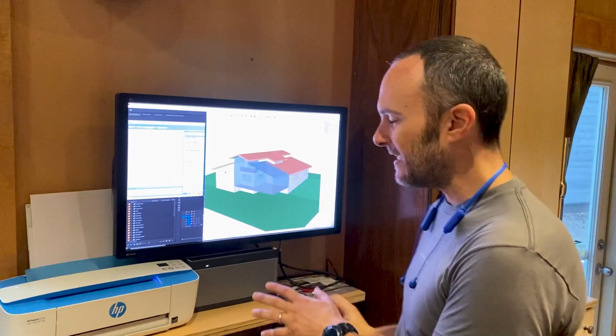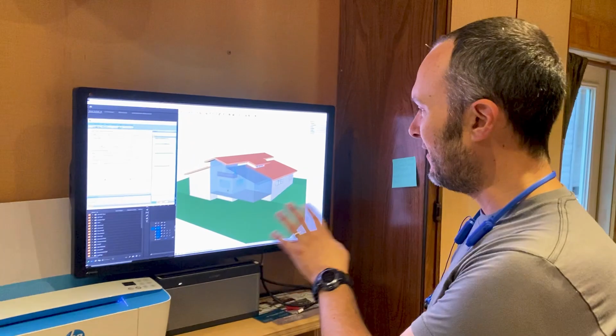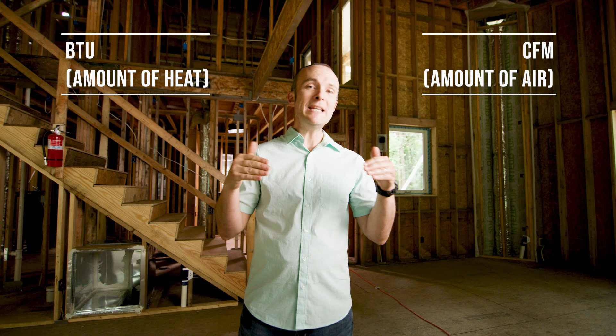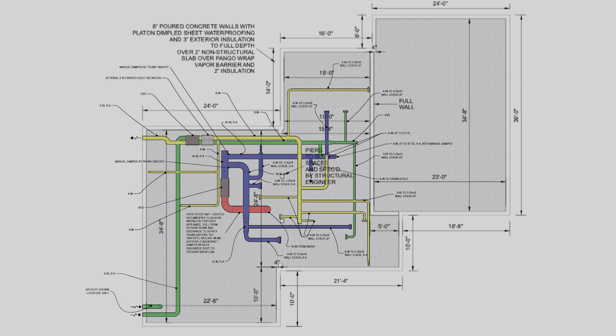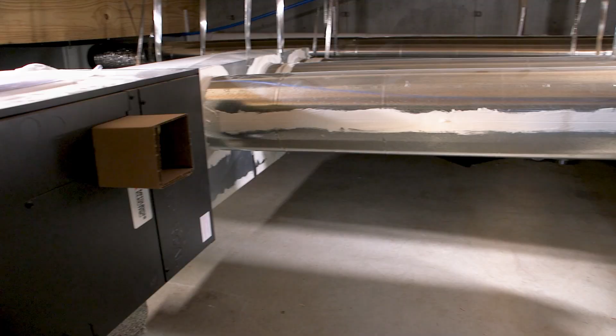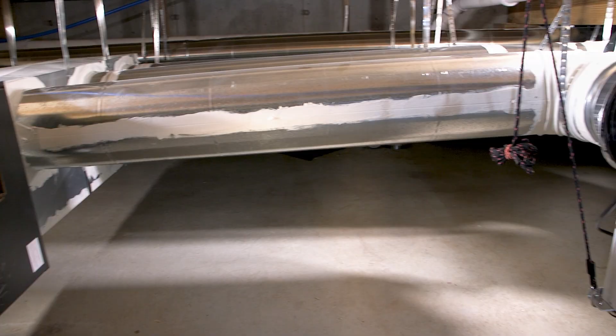First thing to understand is that all this stuff needs to be designed in a computer normally, not necessarily just on a scratch of paper. Essentially, what you need to do is figure out exactly how many BTUs and CFM you need to deliver to each room in the house, which we have done. Then I had someone do the duct design for me and make a map of exactly how big each duct needed to be, exactly how long it should be, how many elbows it's going to be expected to take. Because of course, every little turn and downsizing I add to these ducts, if I'm trying to squeeze it through little spaces, it limits the airflow. And airflow is the whole thing in this case of a breathing apparatus for your house.